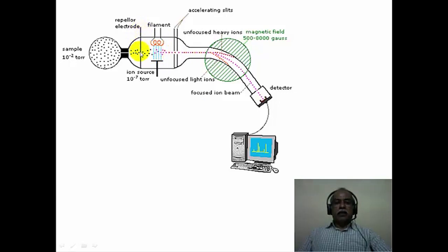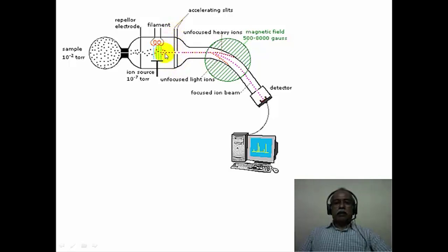There are two electrodes placed here; this is called the repeller electrode. Depending upon the voltage bias, if it is positively biased, the positive ions will get repelled. If it is negatively biased, the negative ions will get repelled, essentially getting attracted to the opposite electrode on the other side of the ionization chamber. The ions get accelerated towards the opposite bias polarity and enter the acceleration zone, where a voltage is applied so that the ions are attracted through a small orifice in the electrode into the magnetic sector analyzer.